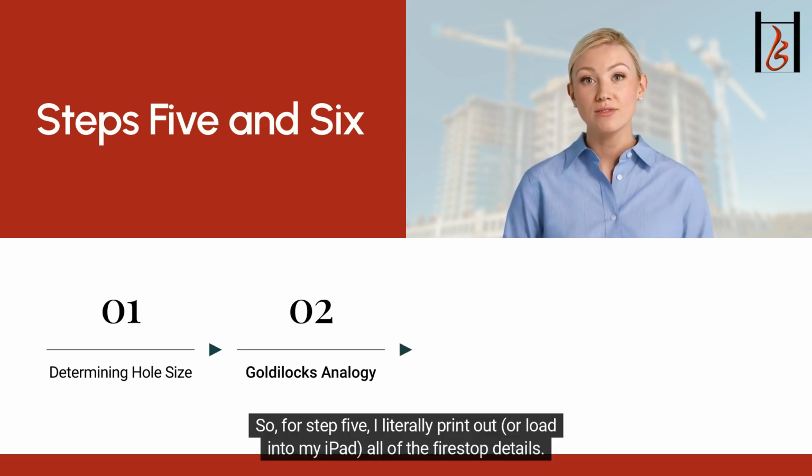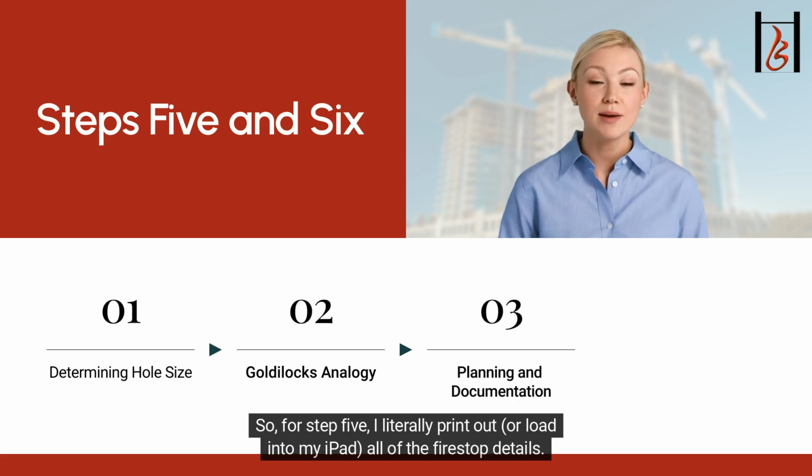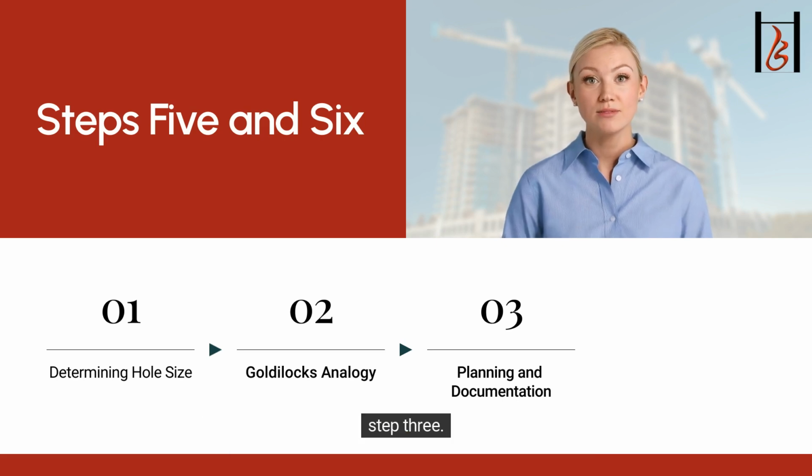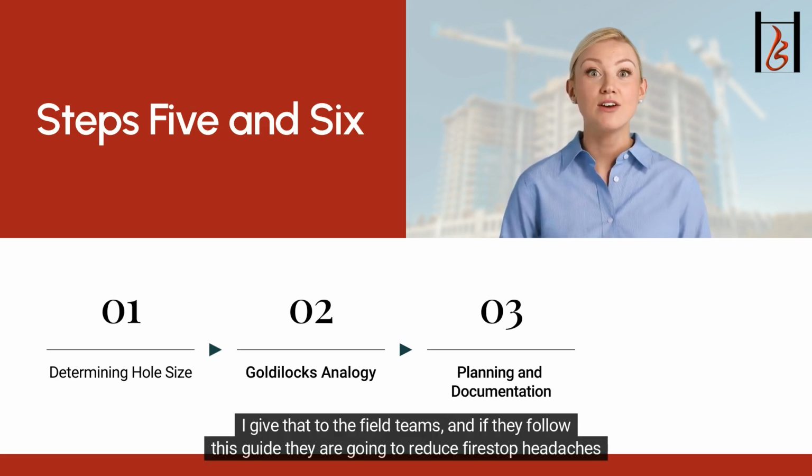So, for step 5, I literally print out, or load into my iPad, all of the Firestop details. Then I highlight the annular space and put the required opening size in a new line on the chart we made in step 3. I give that to the field teams, and if they follow this guide, they are going to reduce Firestop headaches considerably.